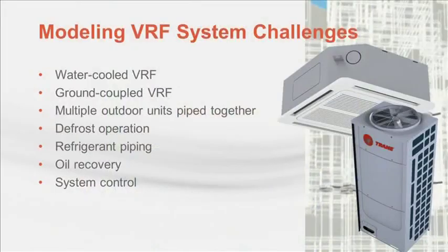Generally speaking, not all simulation programs are capable of modeling VRF or various forms of it. In fact, there are some simulation programs that are not able to model VRF at all, and users may seek workarounds based upon another system that is available in the simulation program. Caution should always be exercised when using workarounds, even if they're prescribed, because unique aspects of system operation may not be captured. Here's a list of potential challenges when modeling VRF systems that we'll explore. And don't forget the issue raised earlier where a single VRF system is modeled that serves the entire building load, even if the building load is larger than a single VRF system.